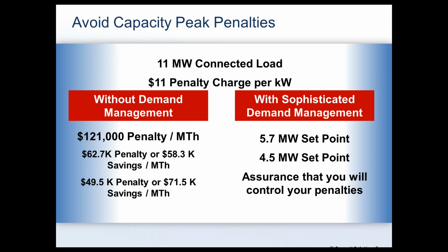all the furnaces at full power simultaneously, we would have hit that 11 megawatt load. With the system that we replaced our old step limiter system with, we were able to operate, and we initially started off at a 5.7 megawatt set point. We were able to reduce our monthly peak penalty charge down to $62,000 per month, or we had roughly a $58,000 per month savings. After we operated for roughly a month at that set point, we drove it down even further to 4.5 megawatt, which gave us some additional savings. We dropped from a 62K penalty down to a 49K penalty.